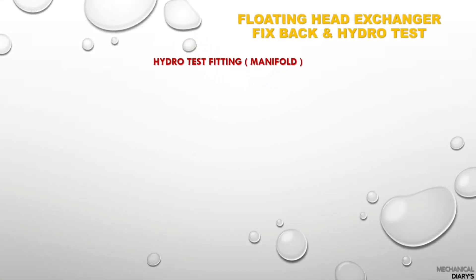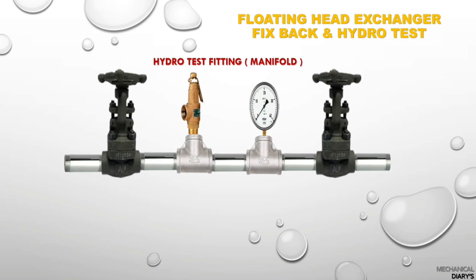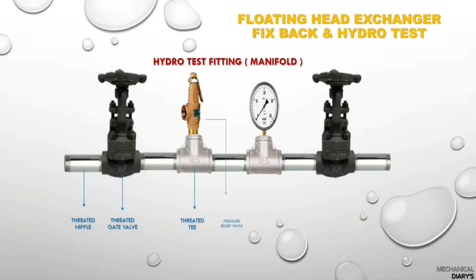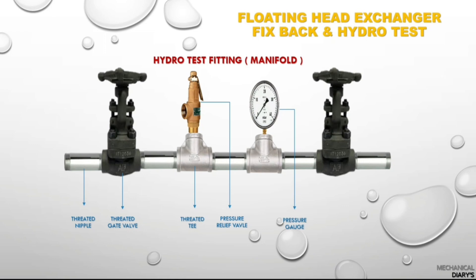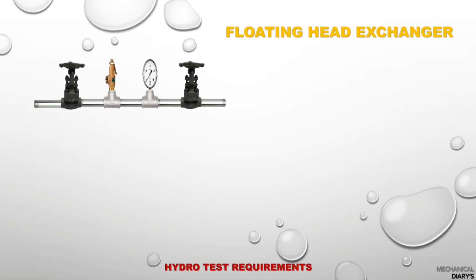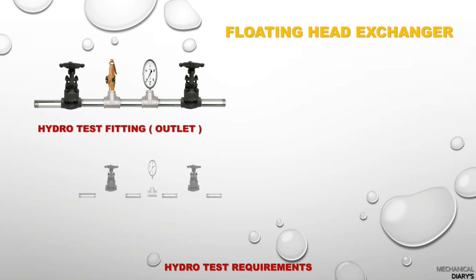While doing inspection activities, you can simultaneously start preparation for the hydrotest. For hydrotest you need two manifolds. The manifold fitting requires two gate valves, and between these two gate valves you must fix one PRV (pressure relief valve) and a pressure gauge. The pressure gauge tells you how much pressure to apply, and the PRV will open if pressure goes above the test pressure.